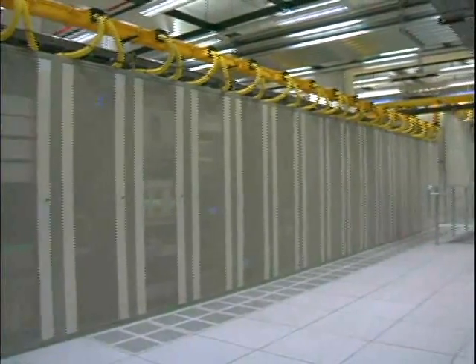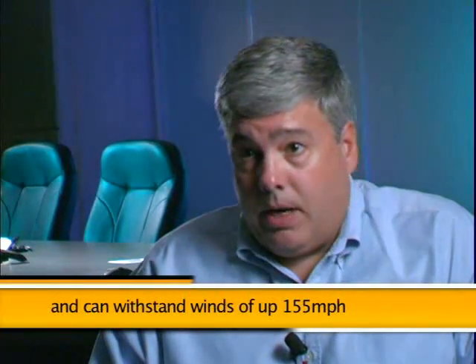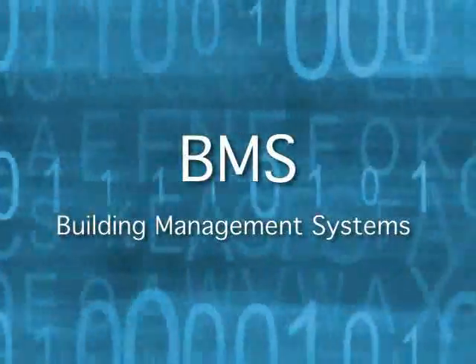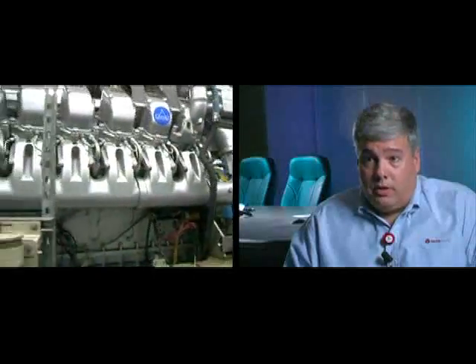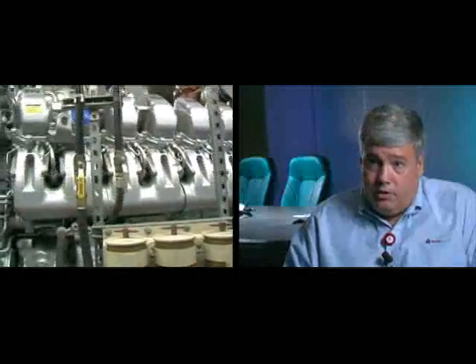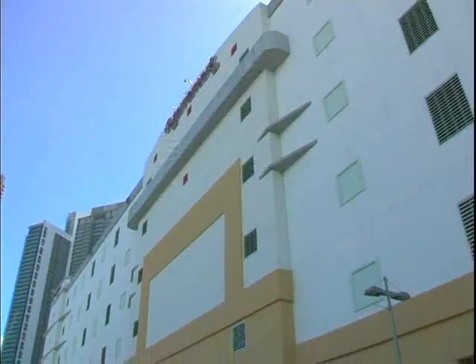Then you've got safety of life issues, meaning fire suppression and emergency power-off systems, so if something happens you can put the fire out or cut the power so people don't get hurt. On top of that you have BMS, Building Management Systems, which means we monitor the cooling, power, security and everything else throughout the facility so we can trend it over time for capacity utilization, installing additional capacity ahead of customer need.